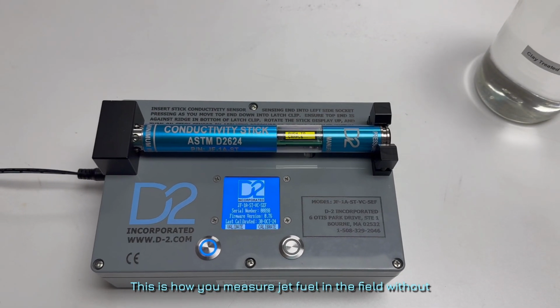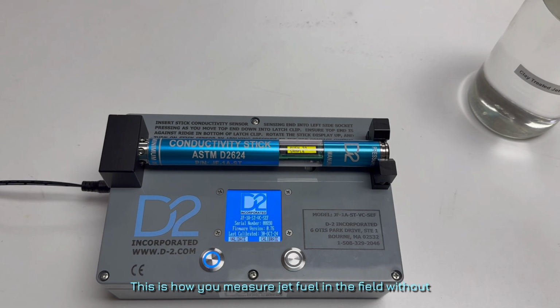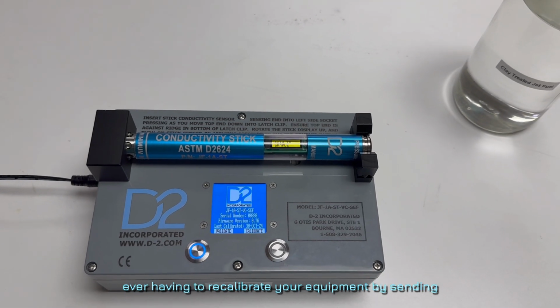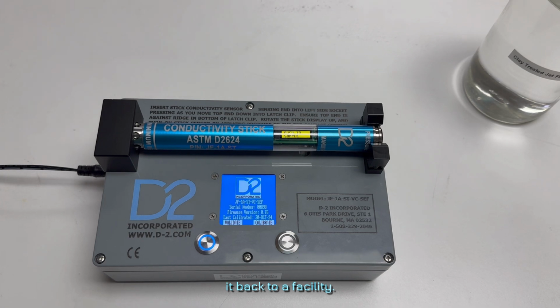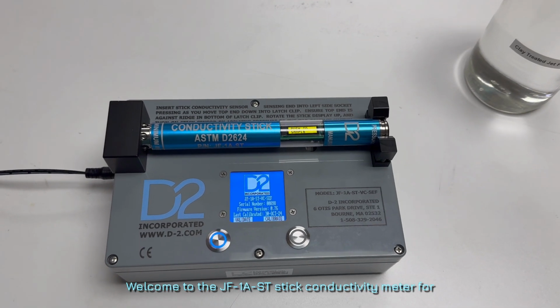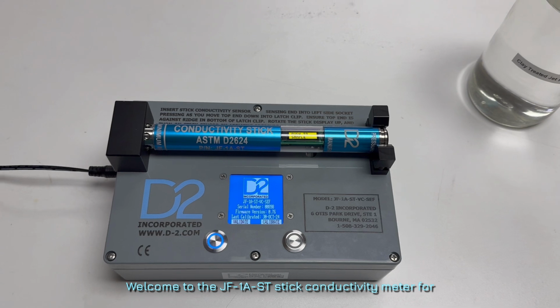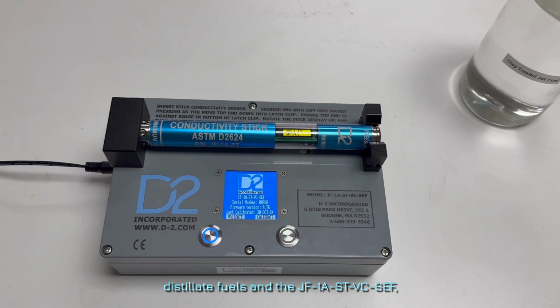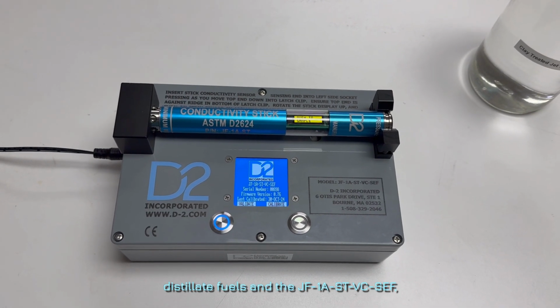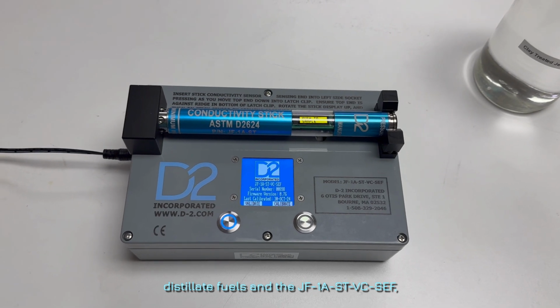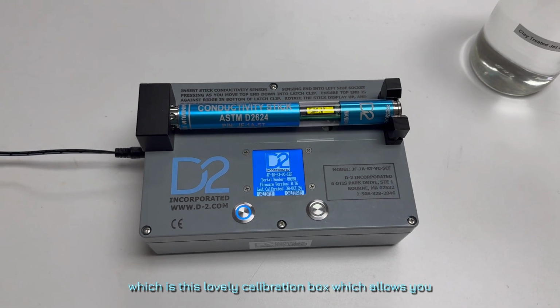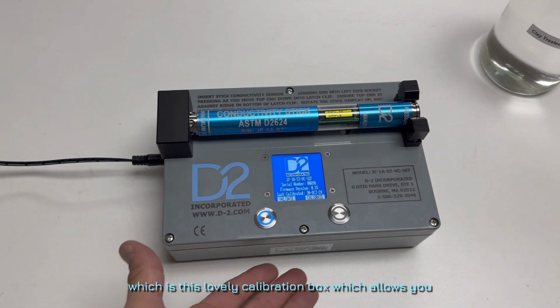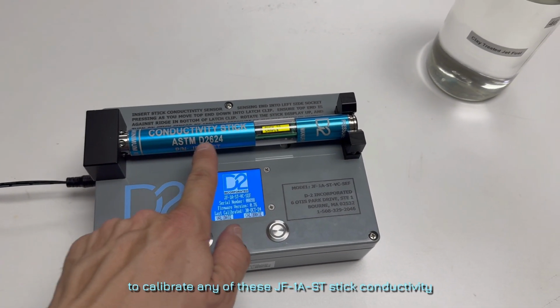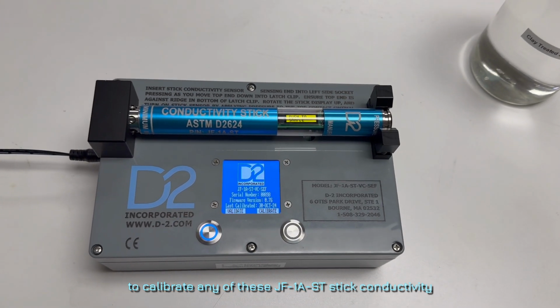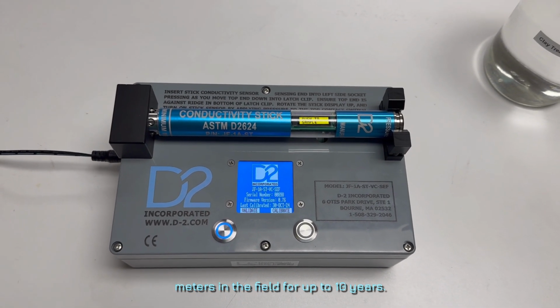This is how you measure jet fuel in the field without ever having to recalibrate your equipment by sending it back to a facility. Welcome to the JF1A ST stick conductivity meter for distillate fuels and the JF1A ST VC SEF, which is this lovely calibration box, which allows you to calibrate any of these JF1A ST stick conductivity meters in the field for up to 10 years.